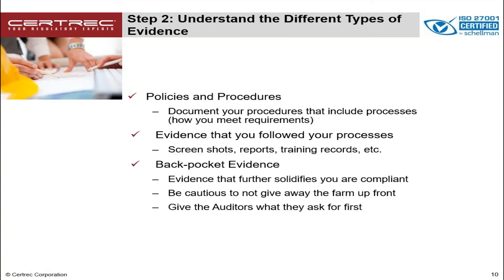Step two includes understanding the different types of evidence that auditors will want to see. The first type are your policies and procedures — documentation that provides evidence you have processes in place that proves how you meet the standard. The second type includes evidence that you followed those processes, such as screenshots, reports, and training records that prove you are following those processes and actually meet the intent of the standard and requirements. An actual example would be evidence of your investigation into the operation protection system for PRC-4, as well as the MIDAS submittals and misoperation reports if applicable.